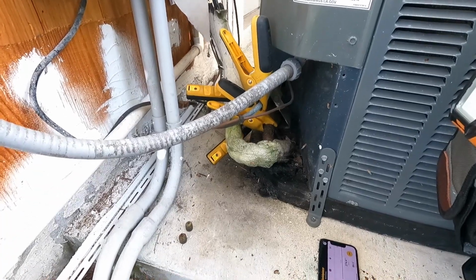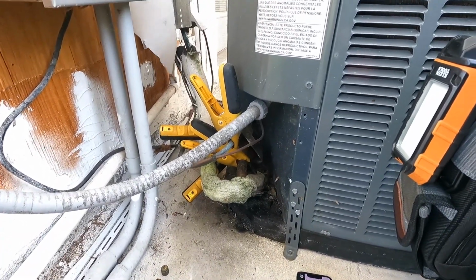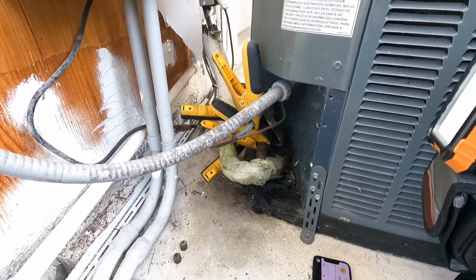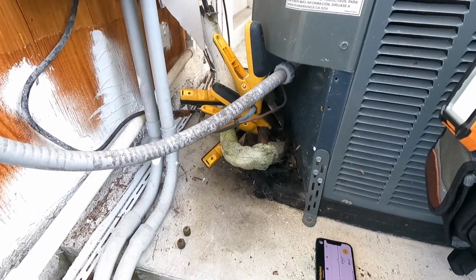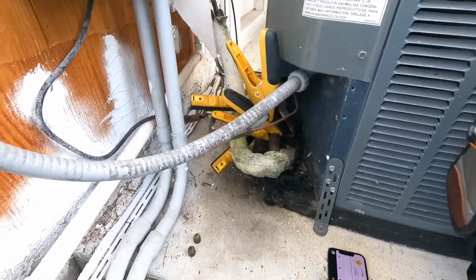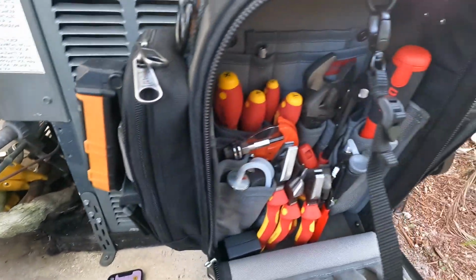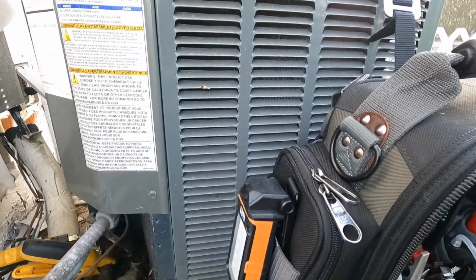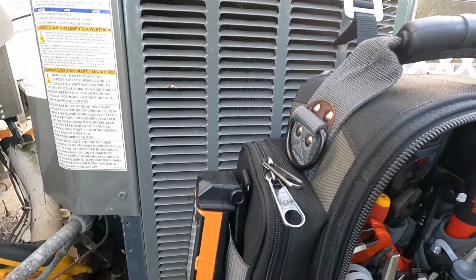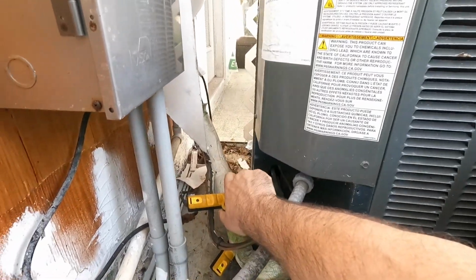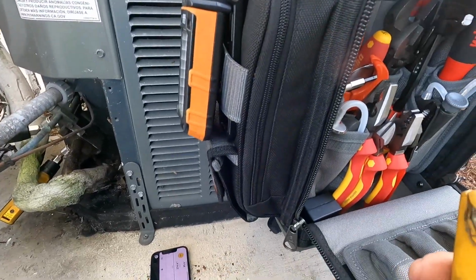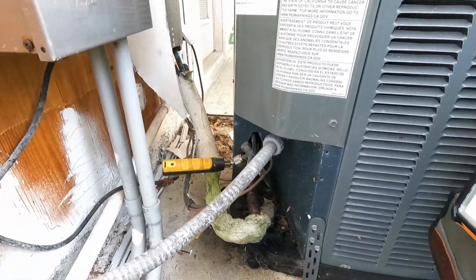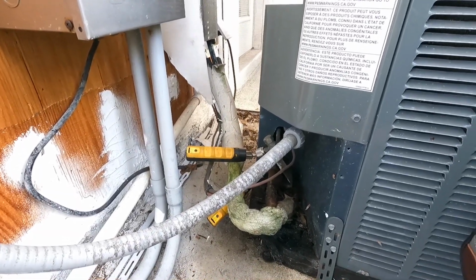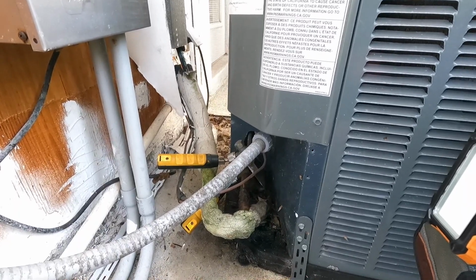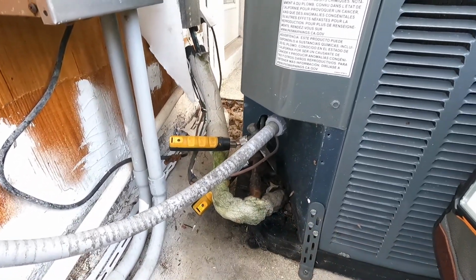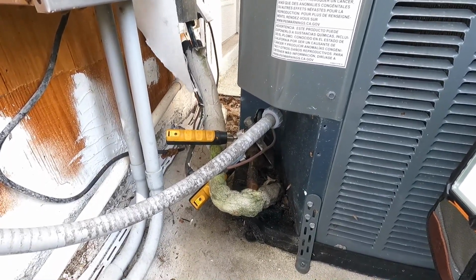See what they want to do, if there's anything more extensive they want to take a look at. Like I said, recommend a maintenance, or at least let them know one needs to be done at some point. Drain line doesn't have any water coming out of it, so could probably use a good cleaning. And the outdoor coil, I can see a lot of dirt. It might not be picking up on the camera, but I can see quite a bit of dirt sitting on it. So go ahead and get these off, put them up, go talk to the homeowner and let them know what we found, what we did with the panel, what we fixed, and the recommendations that these things should probably be cleaned up. All this insulation is pretty shoddy too, it wouldn't be a bad idea to re-insulate that as well.